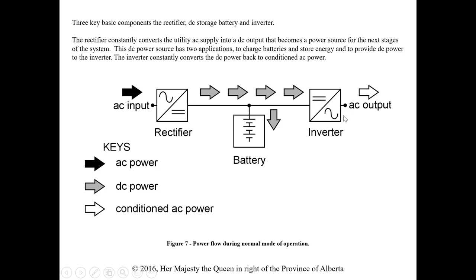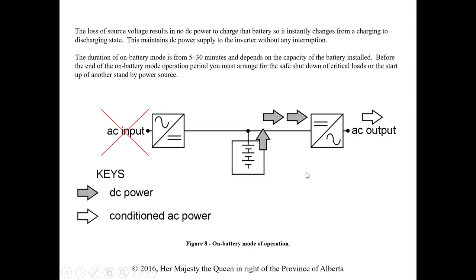Whether we have our AC supply or the battery, the inverter takes DC input and outputs AC. Some loads need a smooth, pure voltage with no spikes or dips. Equipment that doesn't tolerate over- or under-voltages, or requires frequency within an acceptable range, can be served through the inverter output. The AC input from the supply can be full of spikes and irregularities, so we use the inverter to supply conditioned, smooth AC output.